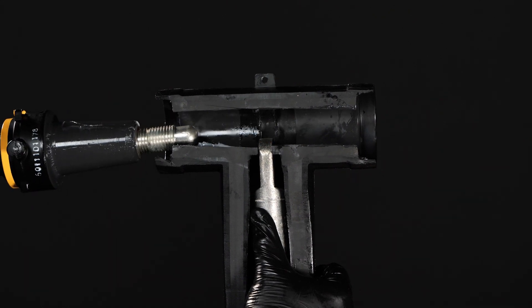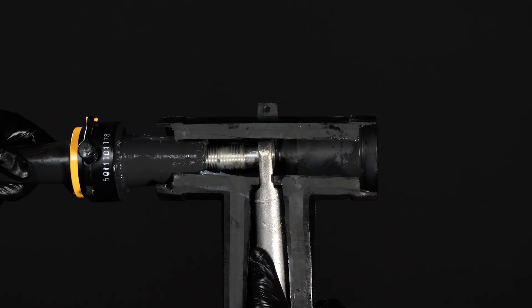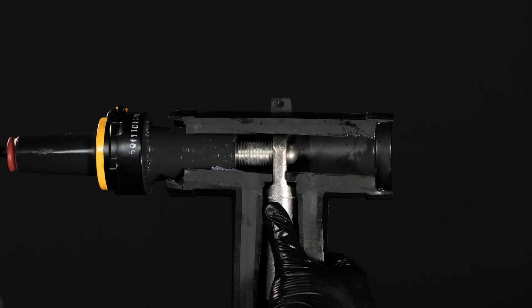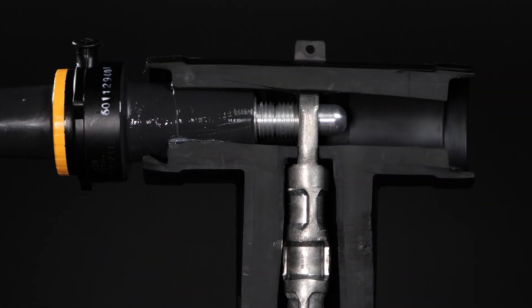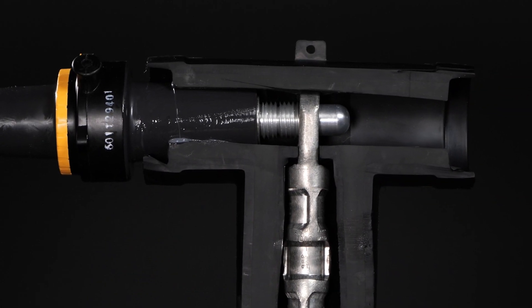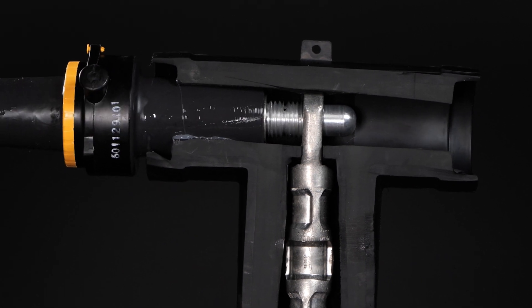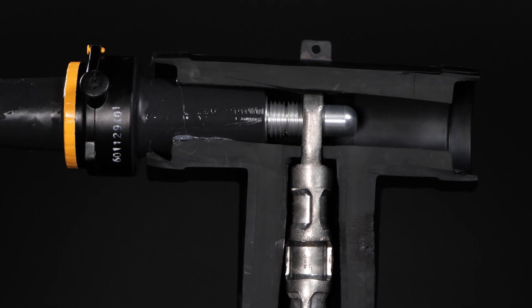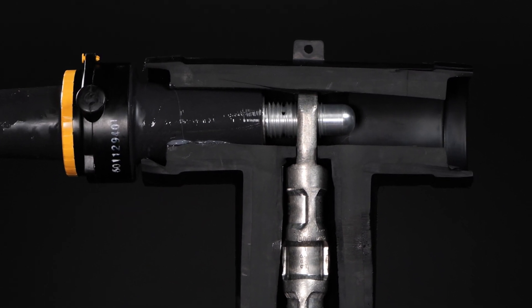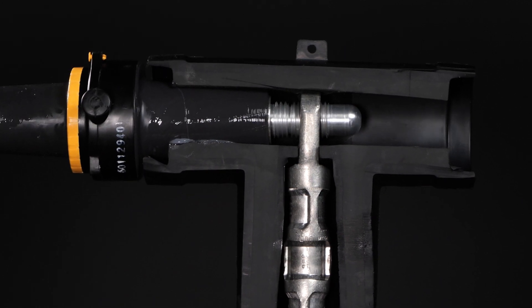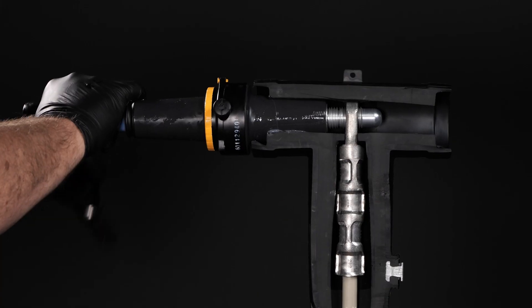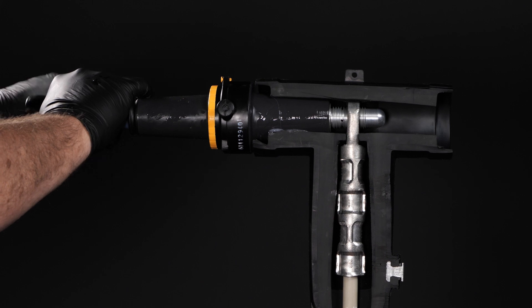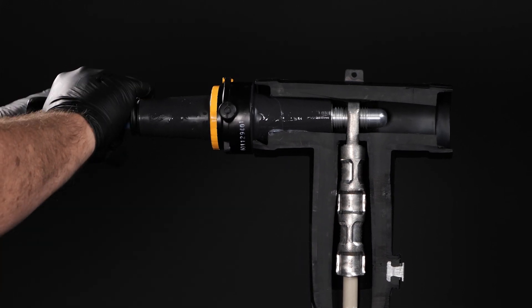The SureTap design eliminates this mistake by attaching itself directly to the lug. Once threads are engaged, insert your 5-16 hex tool inside the SureTap and begin to tighten the SureTap onto the lug. The bullet nose is designed so the threads engage before rubber-to-rubber contact and will not shear unless it is threaded properly into the lug.